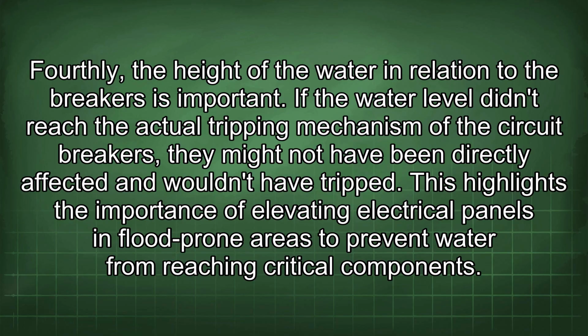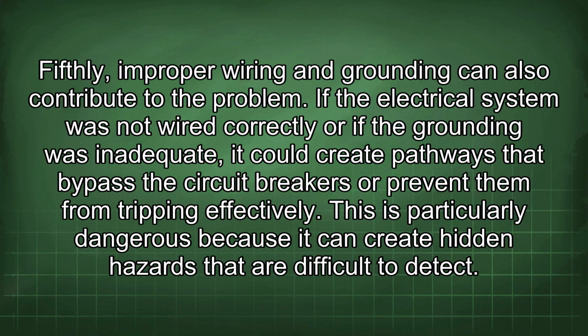Fourthly, the height of the water in relation to the breakers is important. If the water level didn't reach the actual tripping mechanism of the circuit breakers, they might not have been directly affected and wouldn't have tripped. This highlights the importance of elevating electrical panels in flood-prone areas to prevent water from reaching critical components. Fifthly, improper wiring and grounding can also contribute to the problem. If the electrical system was not wired correctly or if the grounding was inadequate, it could create pathways that bypass the circuit breakers or prevent them from tripping effectively. This is particularly dangerous because it can create hidden hazards that are difficult to detect.